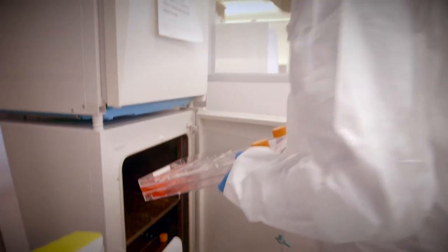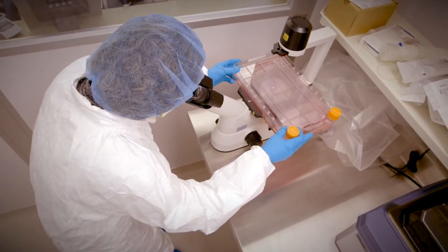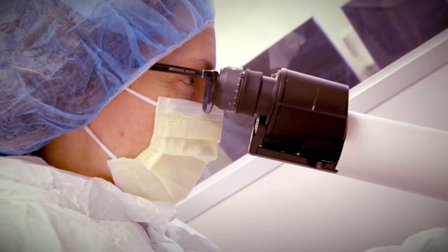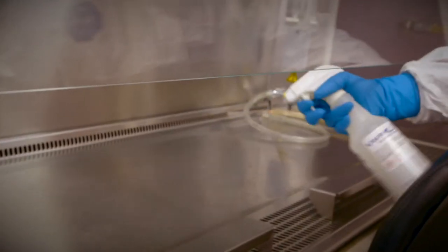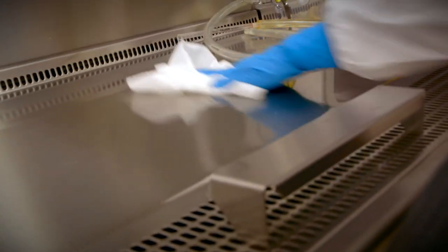The facility is unidirectional flow and uses interlocking doors to maintain proper pressure differential and workflow. Cell manufacturing in this space primarily uses open systems such as flasks, cell factories, or gas permeable bags. In order to work in this environment, staff undergo a lengthy training period to ensure competency in aseptic technique, quality compliance, and protocol-specific procedures.